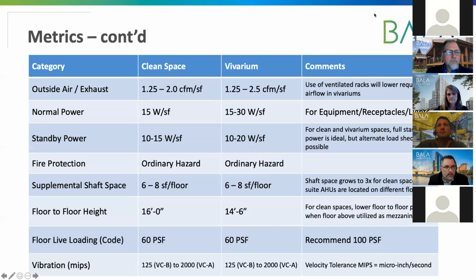Okay, next slide. As I mentioned, we're going to take a look at clean space, clean laboratories, and vivariums on this slide. You can see with both clean and vivarium, the outside air exhaust requirements are pretty close to what you see in a typical lab. On the clean space, it's essentially the same. The amount of outside air is going to vary based on the type of work being done, as far as if you have a high fume hood density or a low fume hood density.